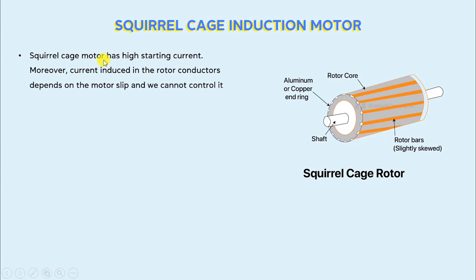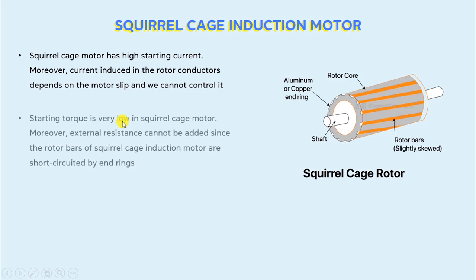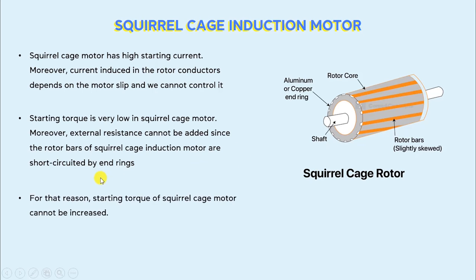A squirrel cage motor has a high starting current. Moreover, the current induced in the rotor conductors depends on the motor speed and we cannot control it. In the case of a squirrel cage induction motor, we cannot control the induced current, and they have a high starting current. Starting torque is very low in a squirrel cage motor. Moreover, external resistance cannot be added since the rotor bars of a squirrel cage induction motor are short-circuited by an end ring — this is the aluminum or copper end ring. Therefore, the starting torque of a squirrel cage motor cannot be increased due to the absence of external resistance.